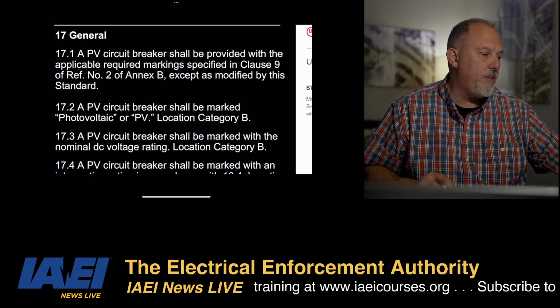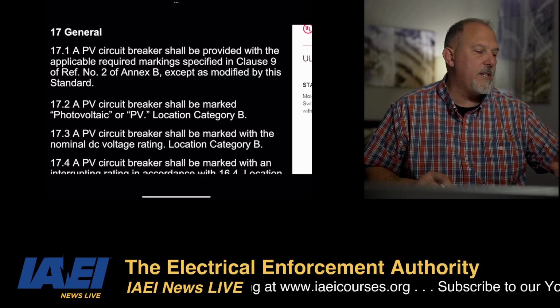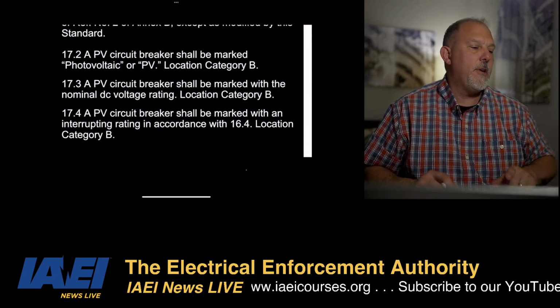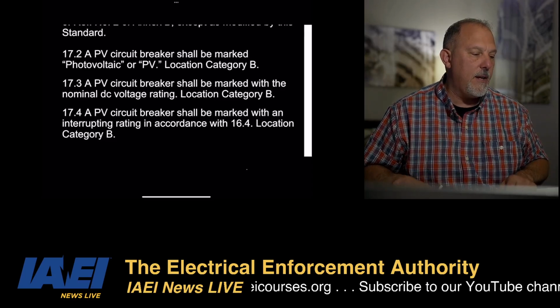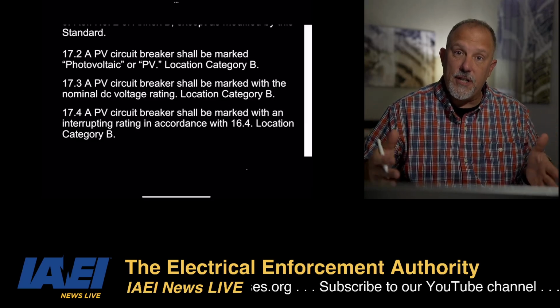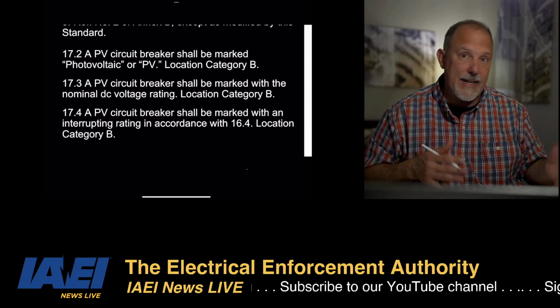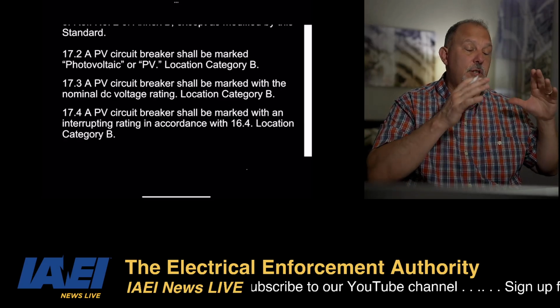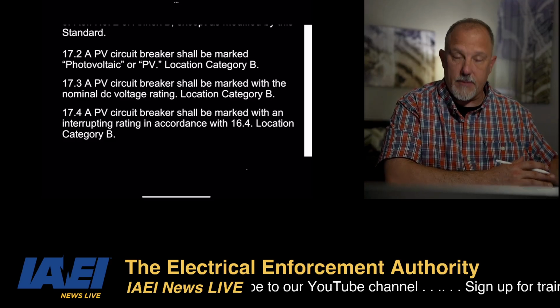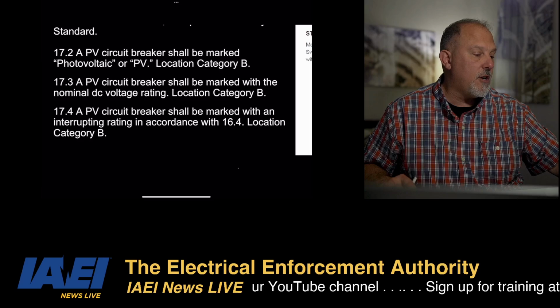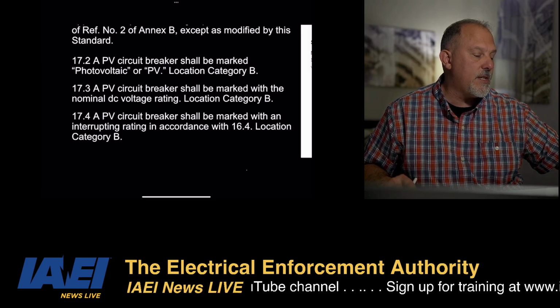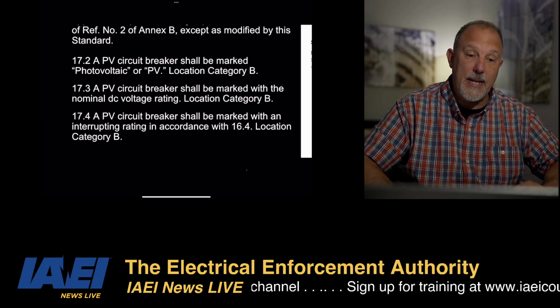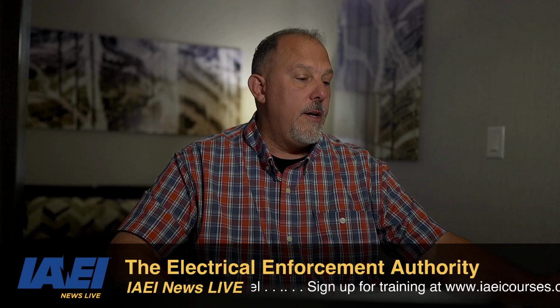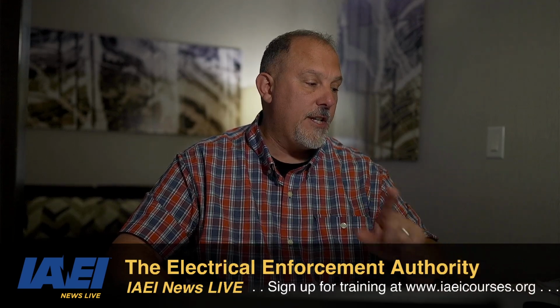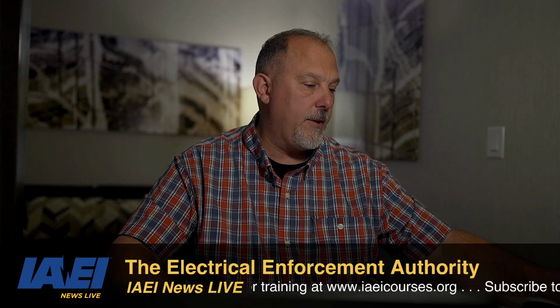A PV circuit breaker shall be provided with the applicable required markings specified in Clause 9. A PV circuit breaker shall be marked photovoltaic or PV, location in Category B. Now, location categories tell you where the markings can be applied. So not only does the UL standard tell you what you need to mark on the product, but also where. PV circuit breakers shall be marked with an interrupting rating in accordance with 16.4, location category B. So suffice it to say that the UL standard is going to give you the marking requirements for these circuit breakers.